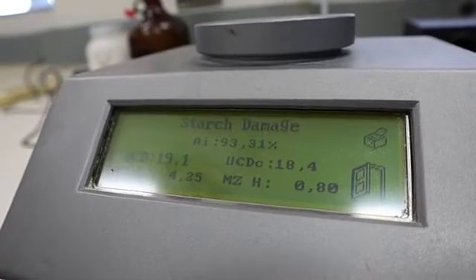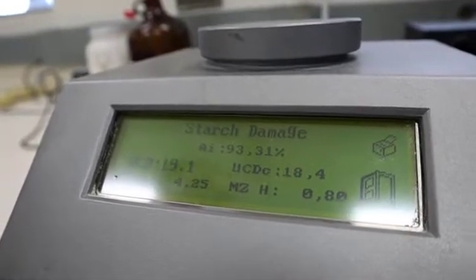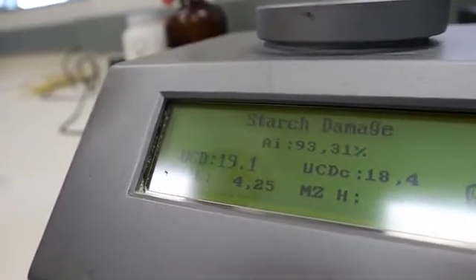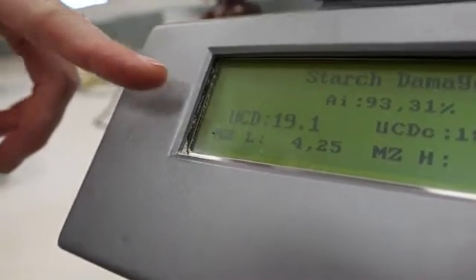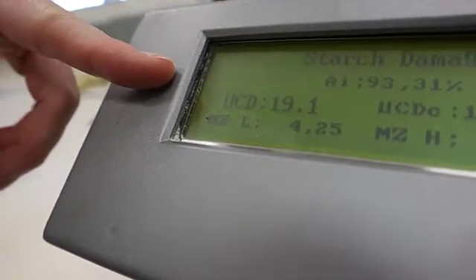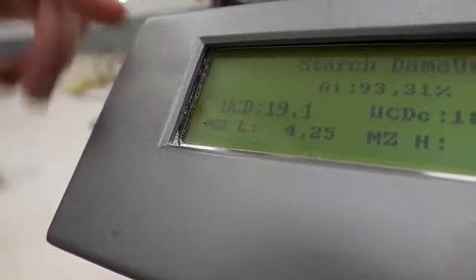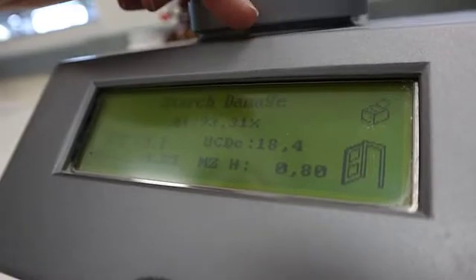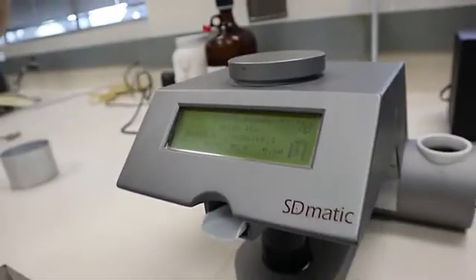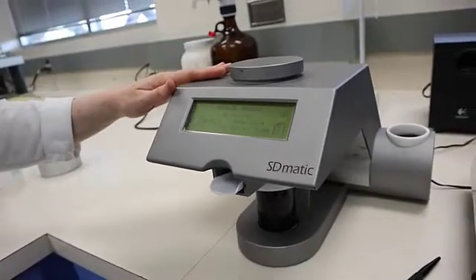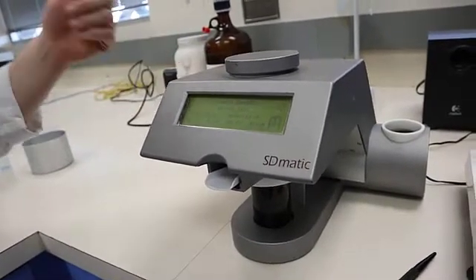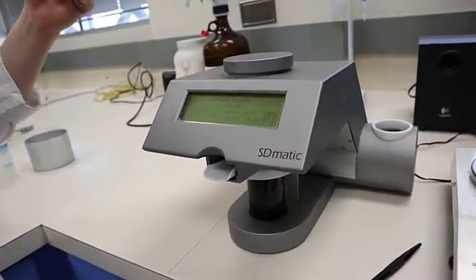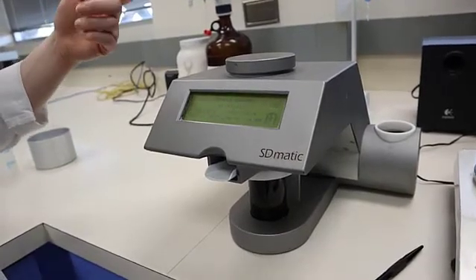The standard reporting value for SD-Matic is the Chopin-Dubois unit, so UCD. Uncorrected, that value is 19.1% for this sample. Corrected for moisture content and protein content, that value is 18.4%. Additionally, you can have an integrated calibration put into the unit as well that provides AACC percent starch damage and Farrand units as well.